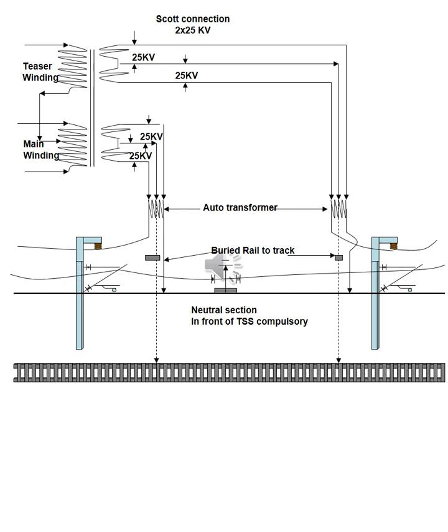But they are installing all new TSS and switching posts. Then the work will be somewhat easier, but the cost will be havoc because you have to purchase land for the TSS and other extra installation, because in the old TSS no parts will be in use. Probably the bus bar size is not adequate, because the power transformer rating is more than the traction transformer. Now we are using 30 by 42 MVA transformers in Southeastern Railway, but here it is 54 MVA. So the bus bar size.